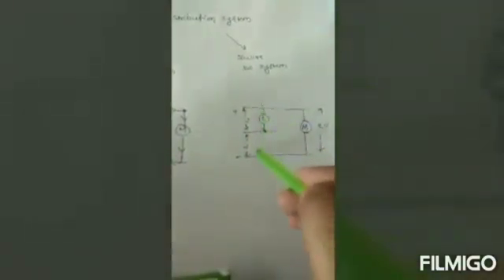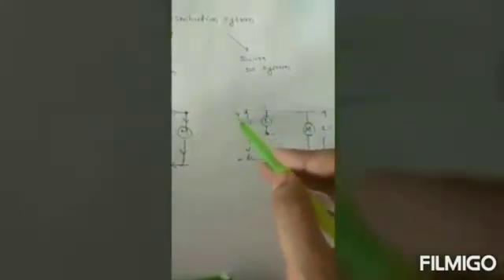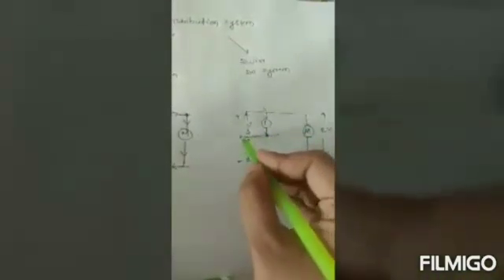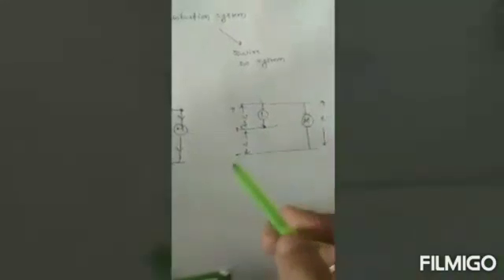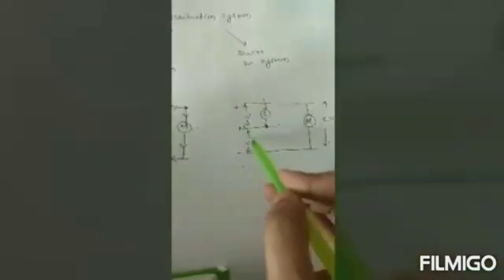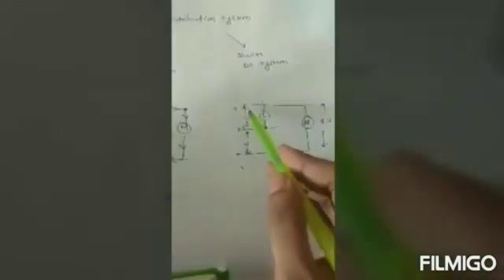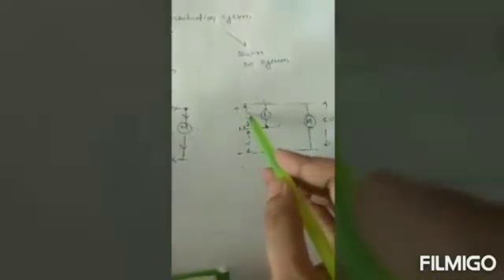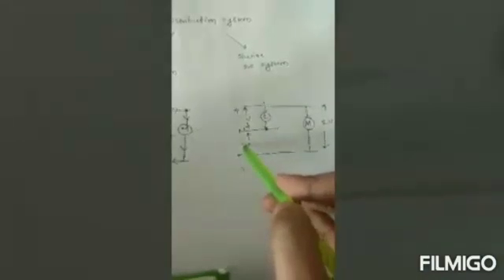Now the second is a three-wire DC system. It consists of two outers and a middle neutral wire. You can see the two outers, that is positive and negative, and the middle wire, which is the neutral, connected with the earth at the substation. The voltage between the outers is twice the voltage between either outer and the neutral wire. In this figure, the principal advantage of this system is the available voltage at the consumer terminal: V between the outer and the neutral, and 2V between the two outers. Loads requiring high voltage are connected across the outers, whereas heating circuits requiring less voltage are connected between the outer and the neutral.